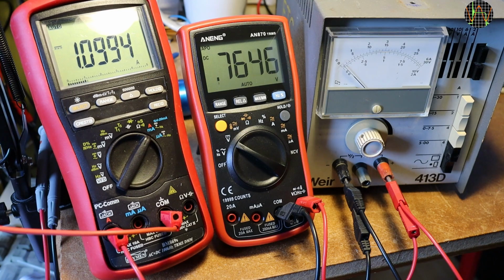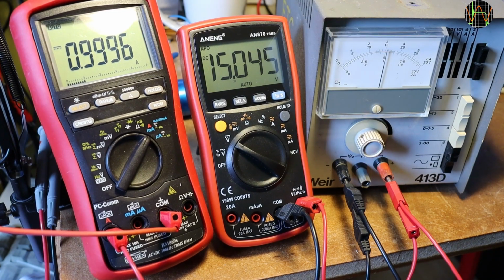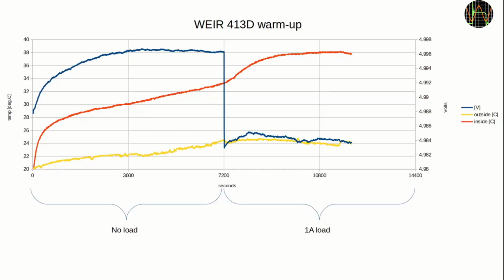This is as discussed earlier, the power supply always uses the lowest voltage and lowest current limit when more than one button is pressed. To verify some of the specs, here's the warm-up behavior. This is the 5 volt range. The blue trace is the output voltage, the red trace the inside temperature, and the yellow trace the outside temperature in degrees Celsius.